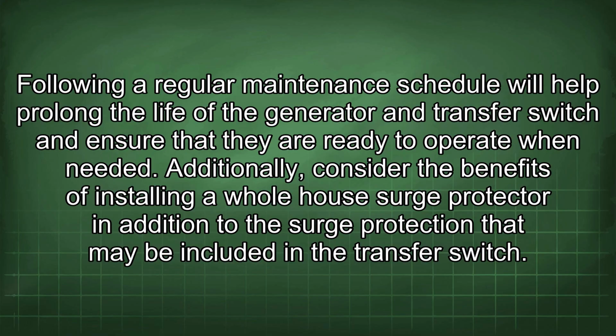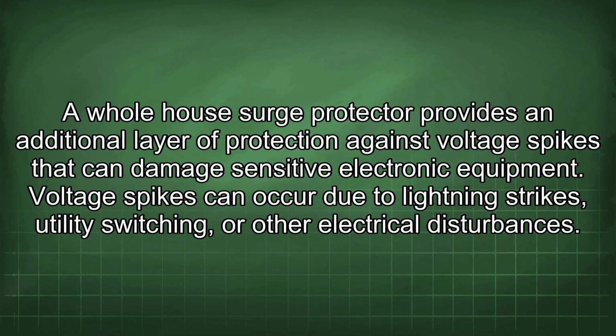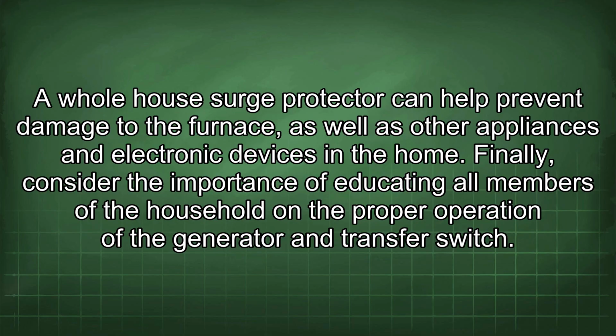Additionally, consider the benefits of installing a whole-house surge protector in addition to the surge protection that may be included in the transfer switch. A whole-house surge protector provides an additional layer of protection against voltage spikes that can damage sensitive electronic equipment. Voltage spikes can occur due to lightning strikes, utility switching, or other electrical disturbances.